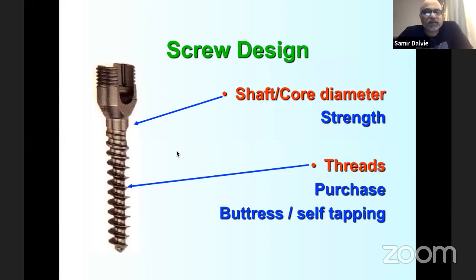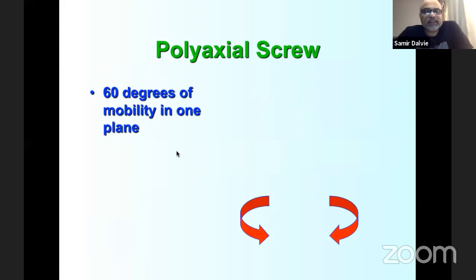Screws have become standardized with shaft diameter and core diameter determining strength, and thread diameter determining pullout strength. Thread types vary by company — variable threads, cortical-cancellous combinations, taper core, and buttress threads that resist backout. Each has pros and cons; a conical shaft is strong but loosens if it backs out even slightly. The variety of thread types indicates no single design is perfect. Polyaxial screws became critical, allowing 60 degrees of mobility to align rods and screws in angulated constructs.